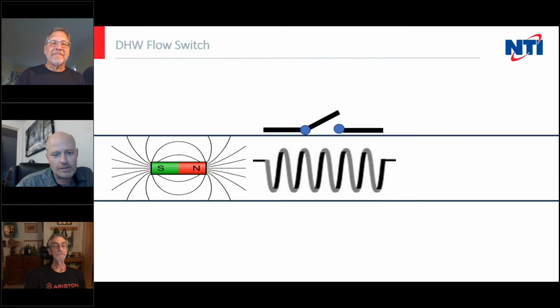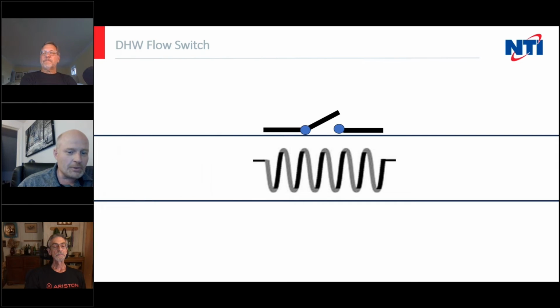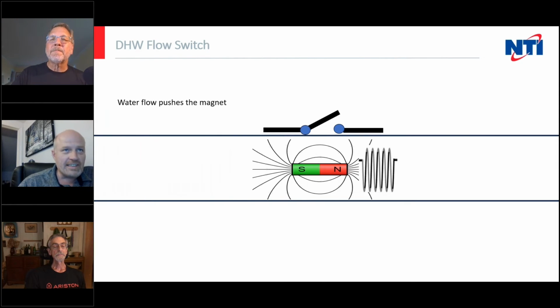Okay, so now we're on to our domestic hot water flow switch. So in the previous poll, we talked about magnets. So in a flow switch, basically they're really simple. The magnet gets pushed, it sits in a plastic housing of some sort. As the water moves through the pipe, the magnet will compress some sort of very fine spring. Once the magnet moves underneath the reed switch, the switch closes.